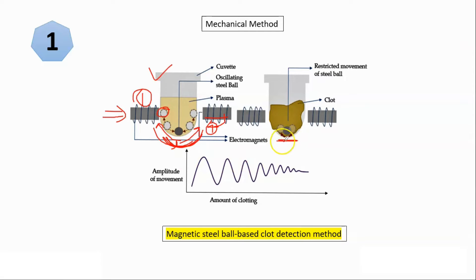Same thing gonna repeat again and again until and unless clot is formed. When clot is formed, the range of motion, range of motion of ball moving in oscillating pattern will be reduced or minimal.